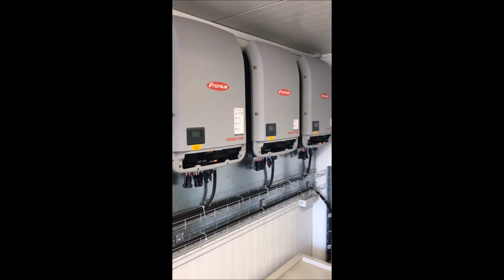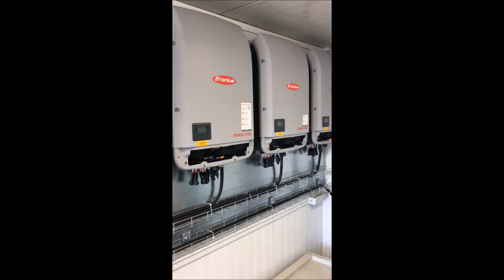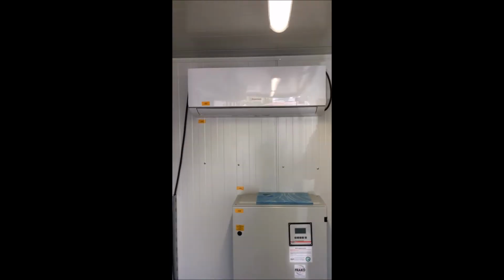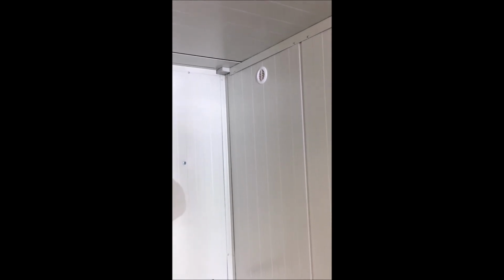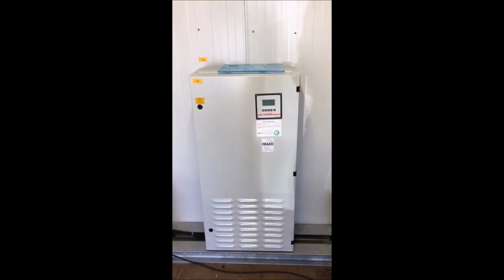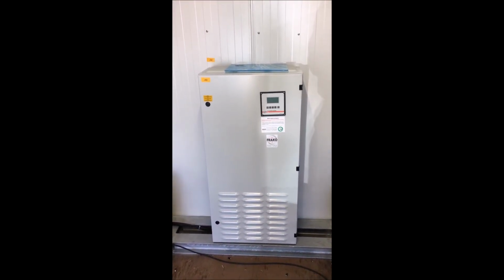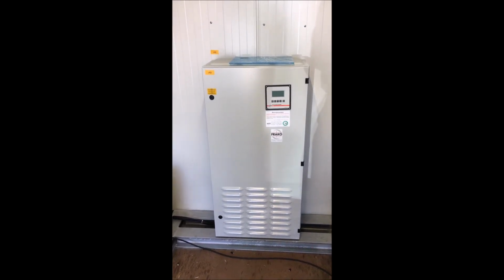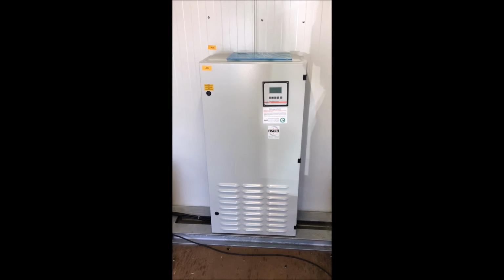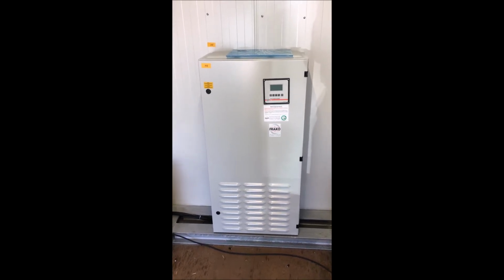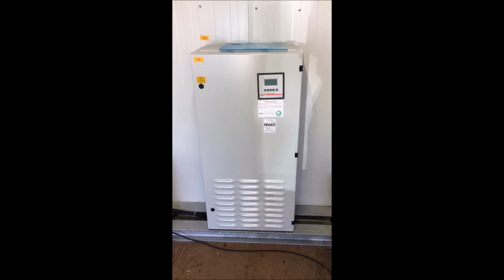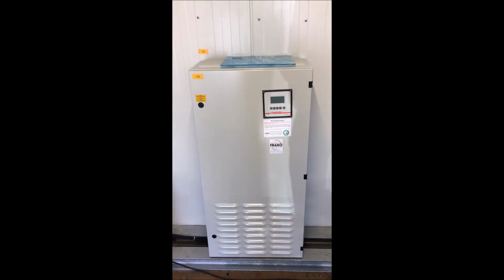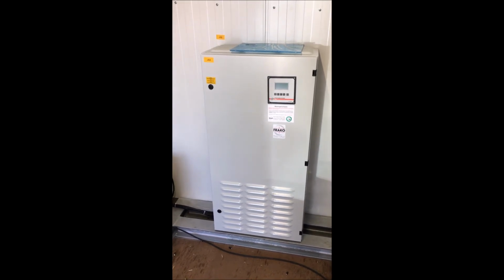Each of the Fronius inverters which you see installed here has a capacity of 20 kilowatt. Of course our containers are air conditioned, they are insulated with 60 millimeters insulation, they have ventilation holes so that any gas could be taken out and evacuated from the container, and of course there is a fan. Now here in the middle, you can see a cosinus phi unit which regulates the cosinus phi in applications where the cosinus phi happens to be less than 0.85. Using this system will actually increase the available power for the load.